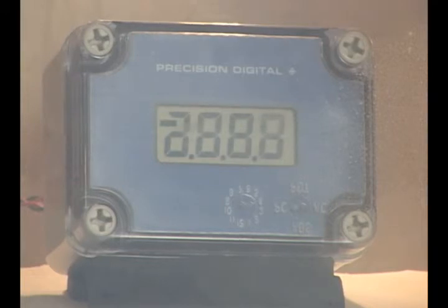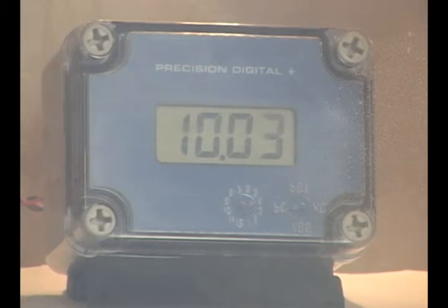If the signal does cut out and the meter turns off, when the signal is reapplied, as I'll do now, despite being in the cold temperature, it will still start. And if during the installation the temperature is so cold that it will prevent the LCD from turning on without the heater being active, the display may be out, but the heater will turn on, and once the enclosure has had an opportunity to warm, the LCD display will appear and display normally, like you just saw a moment ago.